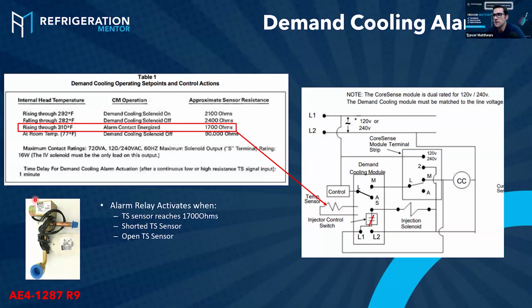I'm going through this. The alarm activates when the TS sensor reaches 1700 ohms. So 310 degrees Fahrenheit. That's around, I think, 150 Celsius, 150, 51 or 52 Celsius. That's alarms energized. And what will happen at that point is it'll switch from M, which is powering your contactor, which goes through your core sense and then energizes your contactor for your compressor. It'll go to alarm. So now I don't have power going through, and the compressor is going to shut off, and it's going to trip on your demand cooling alarm.